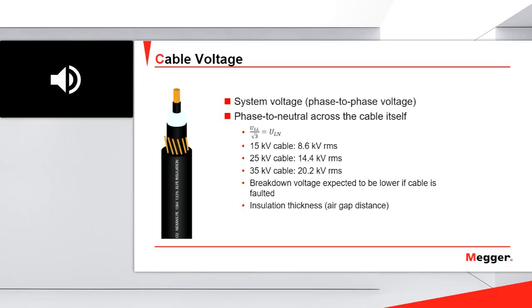Now, cable voltage. When we talk of medium voltage cables, we usually say we have a 15 kV cable, a 25 kV cable, or a 35 kV cable. This is the system voltage, or the phase-to-phase voltage. From the point of view of fault location, what is important for me is the phase-to-ground voltage. For instance, for a 15 kV cable, that phase-to-neutral or phase-to-ground voltage is 8.6 kV. For a 25 kV cable it is 14.4, and for 35 kV cables it is 20.2. So when I need to select a thumper for my cables, keep in mind that the voltage to consider is the phase-to-ground voltage of my cable.